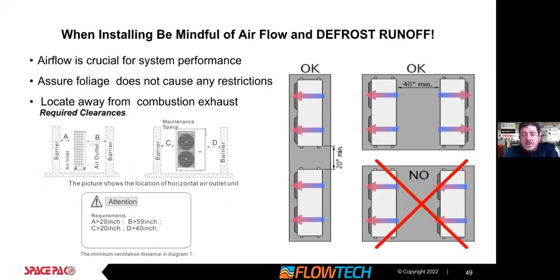We'll talk about multiple unit installations here. The big takeaway is you don't want one unit blowing into the other. It will reduce performance on that. So make sure you either go back to back or side to side with the proper clearances there.